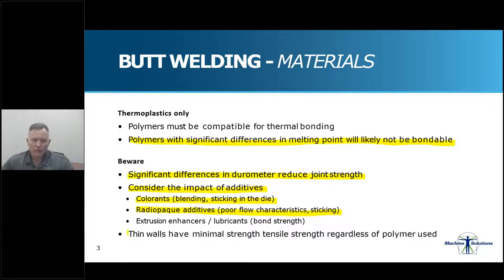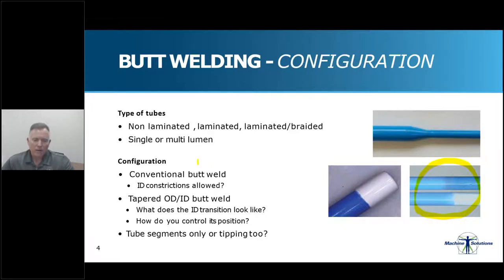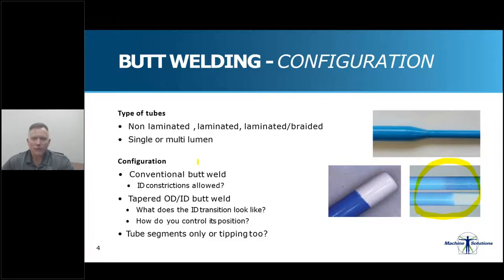Just remember that thin walls have minimal tensile strength regardless of the polymer used. Butt welding can be used to join tubes in various constructions. The simplest is a single lumen extrusion, which can be constructed of multiple layers of polymer produced by coextrusion or lamination techniques. A layer of metallic or polymeric braiding can be included in lamination to provide kink or torque resistance. Laminations usually have a wider outside diameter tolerance range than simple extrusions and provide less surface area for the materials to thermally bond. OD variation is a specific concern to keep in mind when creating your design and establishing your performance specifications.